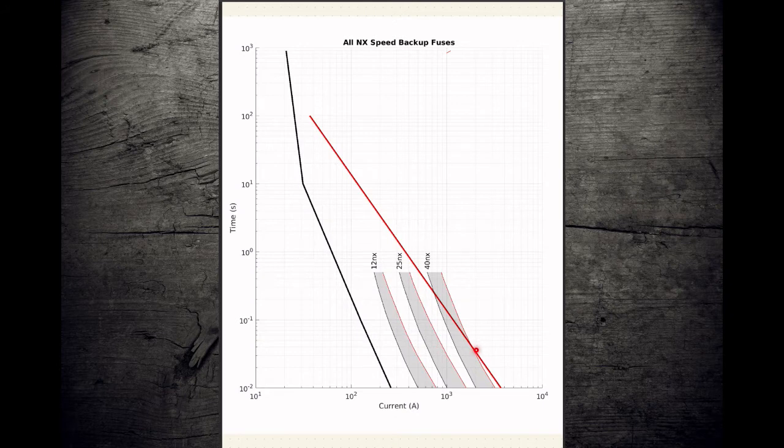23 milliseconds, no, 33 milliseconds. It will stop protecting this transformer, right? So that's 10, 20, 30, so right around 33 milliseconds. It's going to stop, which is 2 cycles. It's not guaranteed to have cleared before the transformer is damaged.